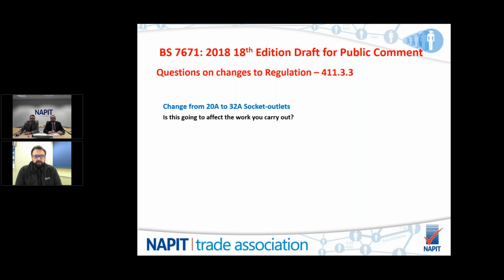No, guess not. Okay, so a couple of questions we've had. The first one is, I install a lot of 32 amp commandos in data centers. Does that mean they've all got to be RCD protected? With this change to the regulation, those types of socket outlets would fall under this regulation, and it would mean that all these 32 amp commando type sockets would have to have RCD protection. That's one of the effects of the change and would affect your workload. So then you'd be recommending to your client that all 32 amp socket outlets would have to have RCD protection.